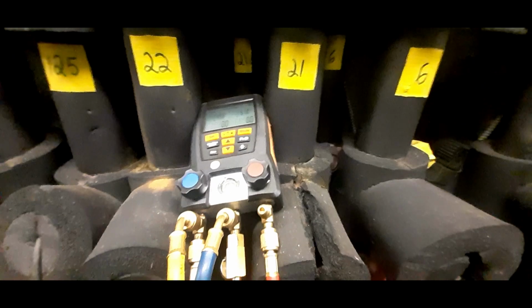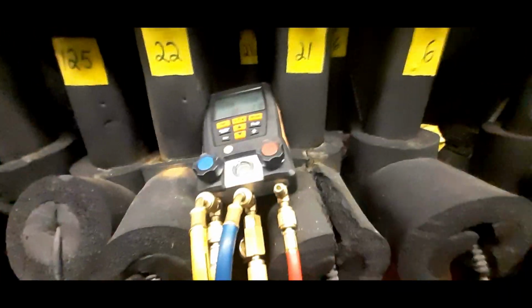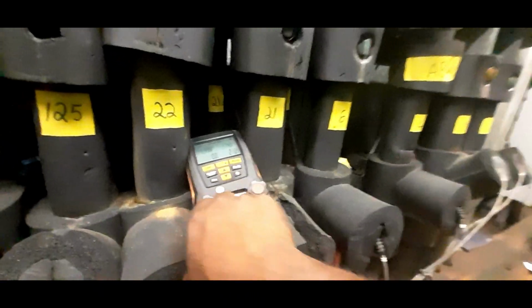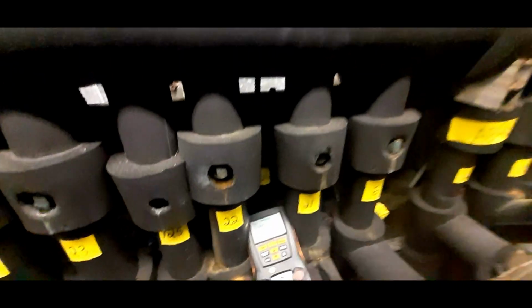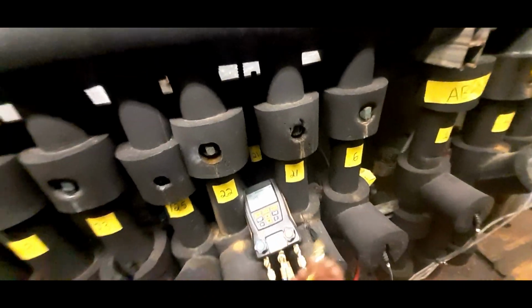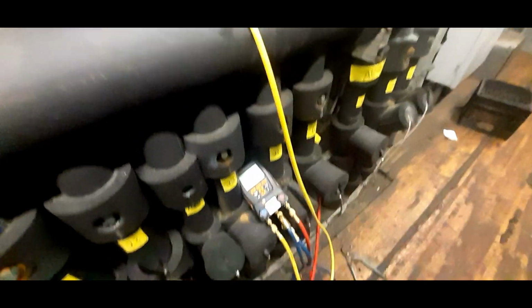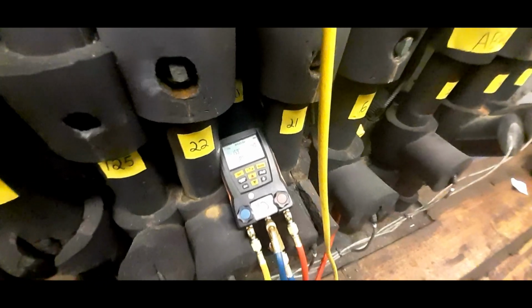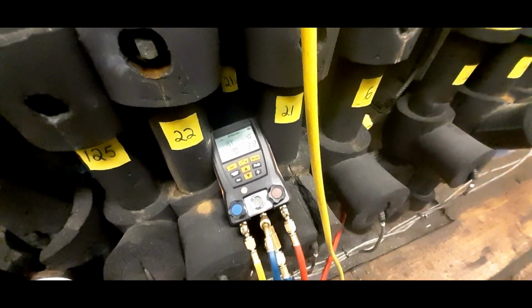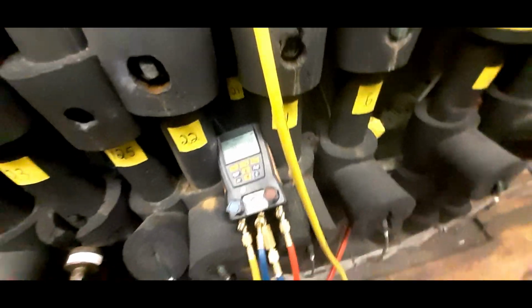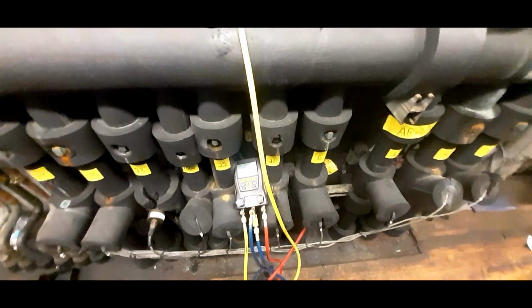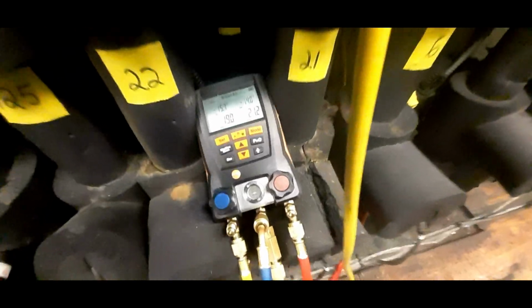Hook up. We're at zero on our gauges before hooking up. So right now we got, what, 21 on that circuit. Let's see what it's reading at the transducer. We're going to hook up here, and they should be reading the same if that valve is 100% open. So what's that, 18, 19, 21? That's 100% open, even though it's off by 2. 19 over 21, so that is open.